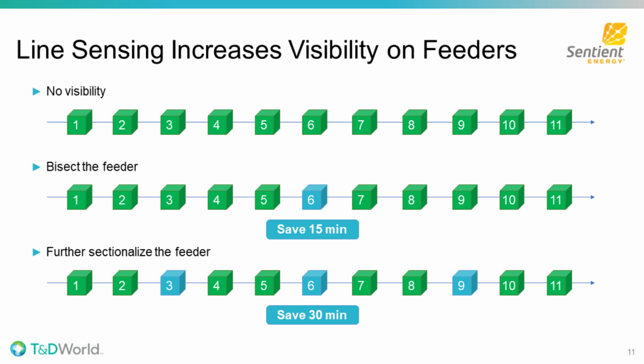If we want to save the crew another step, we add line sensing at cabinets 3 and 9. So now the crew saves 2 steps in their process, or 30 minutes, because they know which quarter of the feeder the fault is on before they arrive.